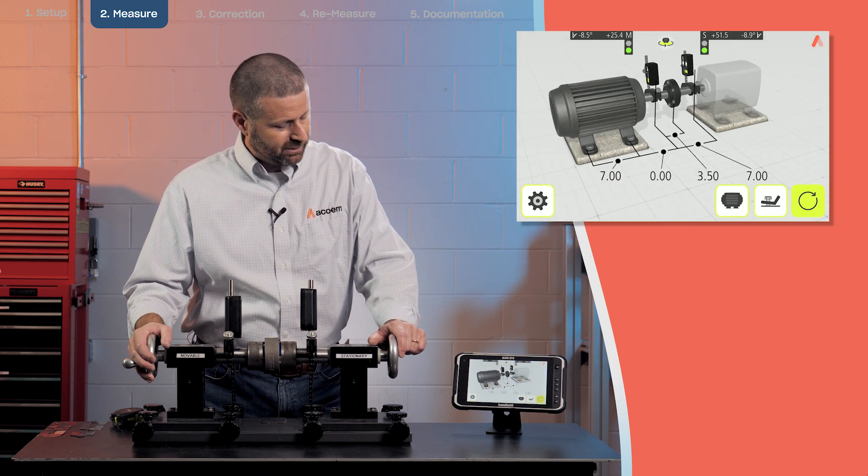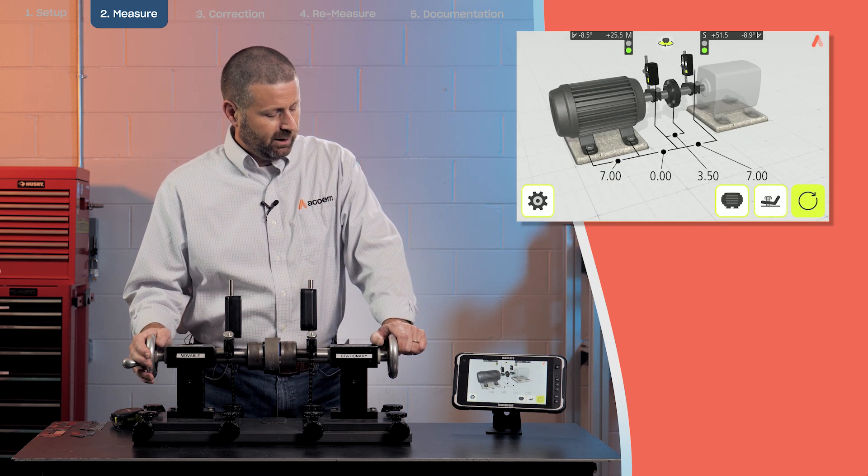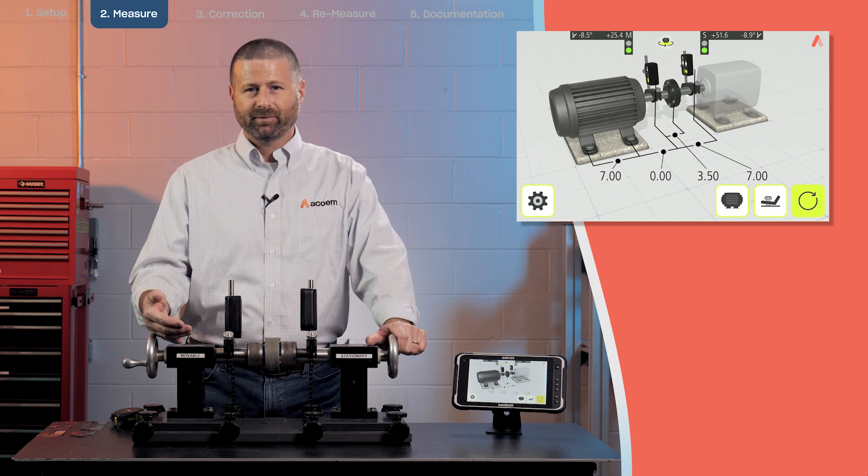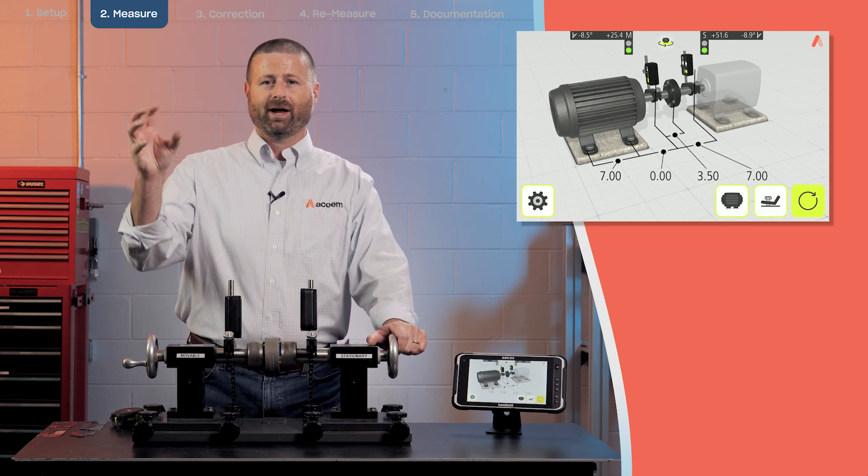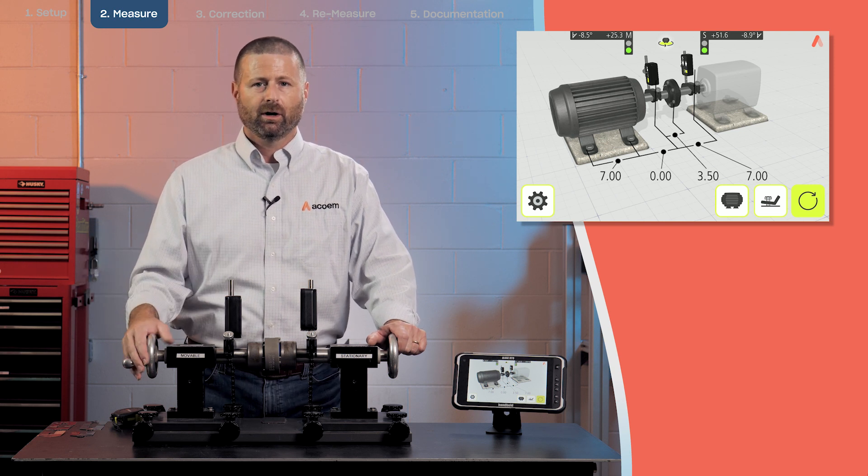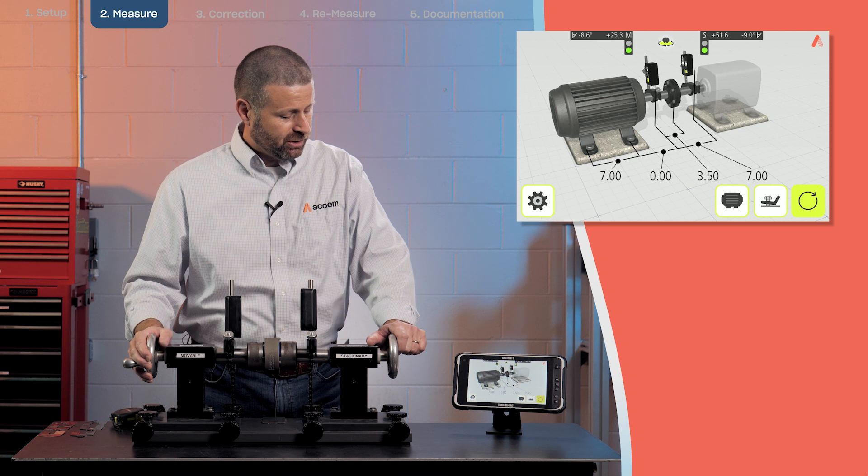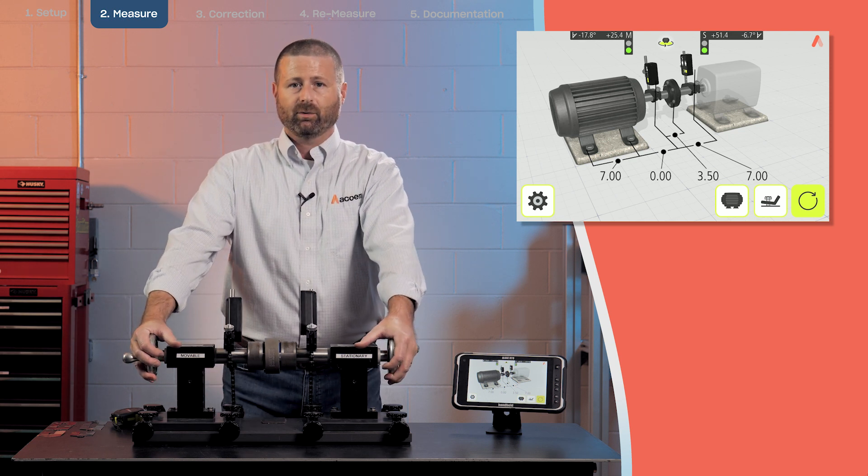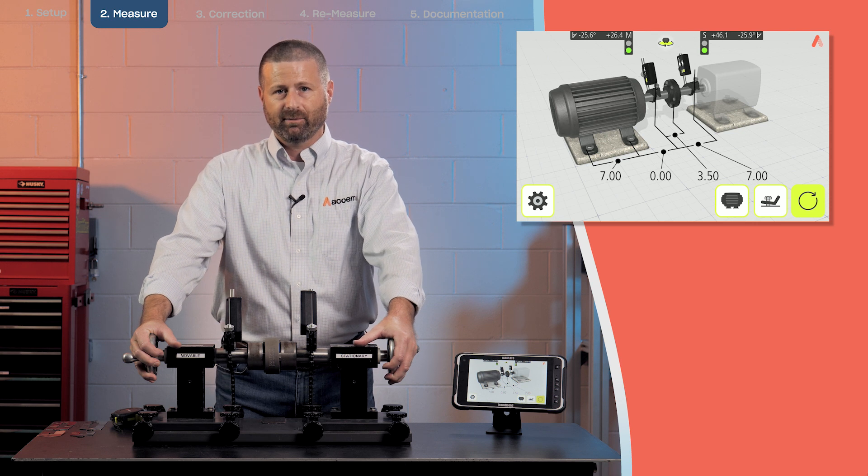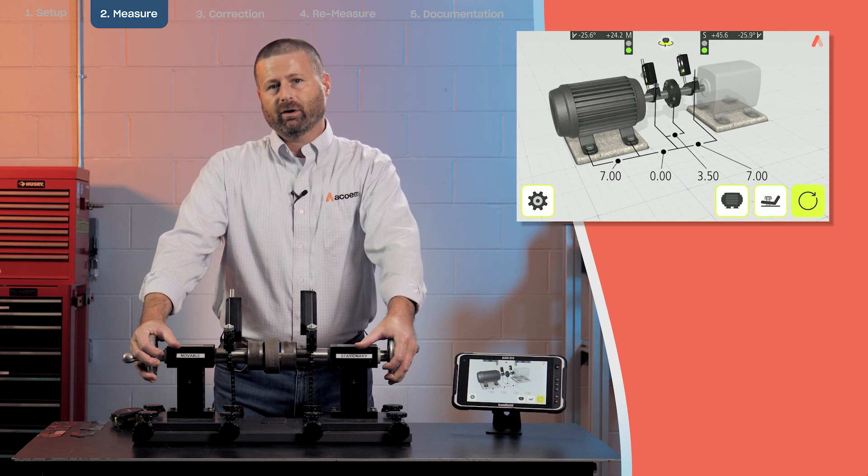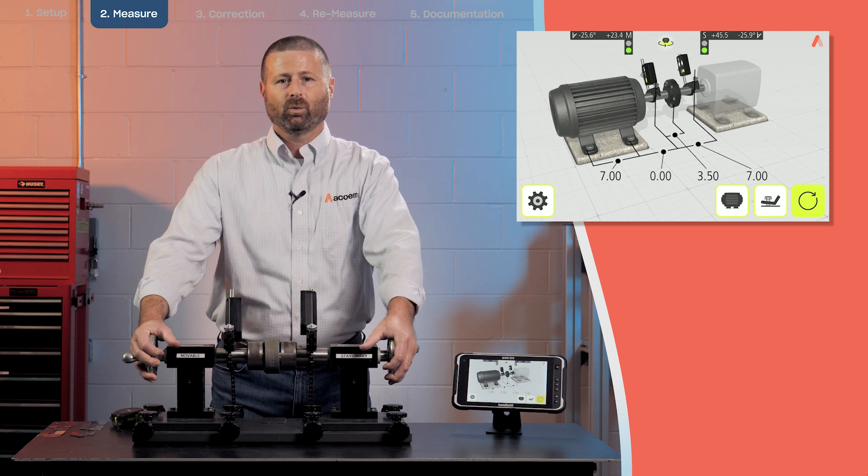So we hit the check box and you'll see each next step of the alignment process is generally highlighted in yellow. That's part of what we call our guide you user interface. So what we're going to do now is something we call a vertizontal alignment. We're going to take one set of shaft alignment measurements and complete both the vertical and the horizontal adjustments in one step.